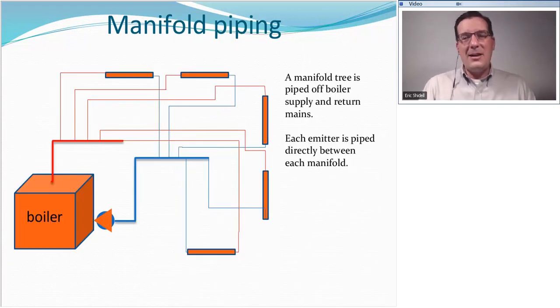The next kind of system is called manifold piping, and this is pretty deluxe here, because now we have basically just one main supply and one main return manifold, and off of that manifold is a branch line that is dedicated to each emitter. So here we can follow the supply, and it comes off and goes to one emitter and comes back to the return. Comes off the supply, goes to the next emitter, and back to the return. In this manner, every emitter gets exactly the right temperature of water. They're all the same temperature of water, and the circulator pump controls the flow through them.